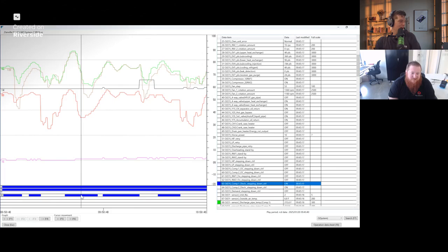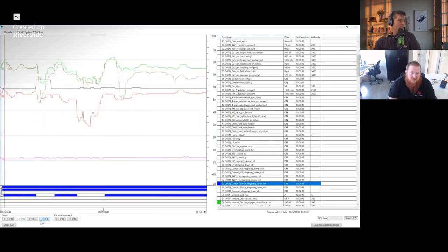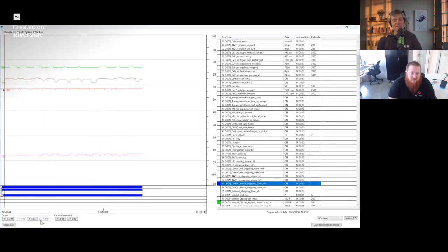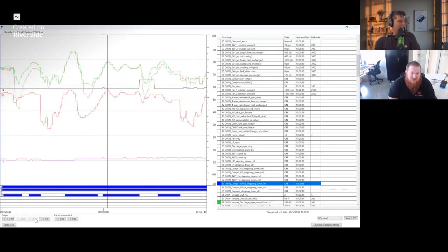You can see here we've got large segments of high discharge step down. This is a lot of red flags. It stays on the entire time towards the end of this data. I would say, Matthew, this is your bad system number 2, but also you've got issues with system number 1. I hate to tell you, but they both have problems. This one is probably a lot worse than the other. And again, no error code.